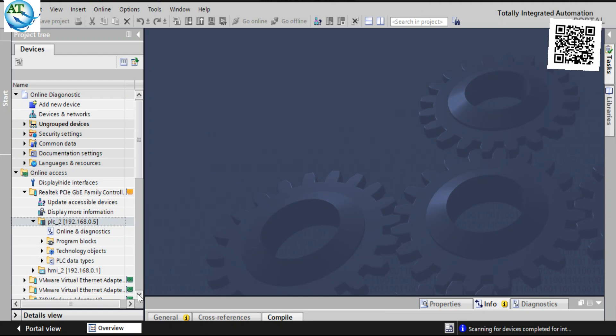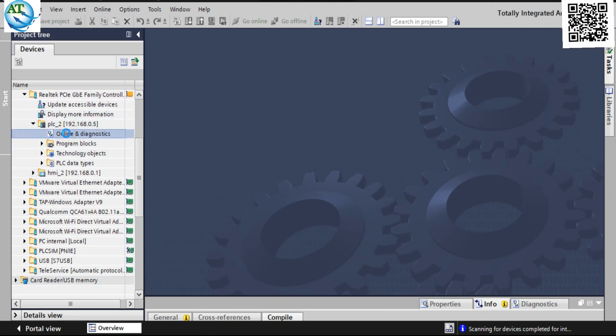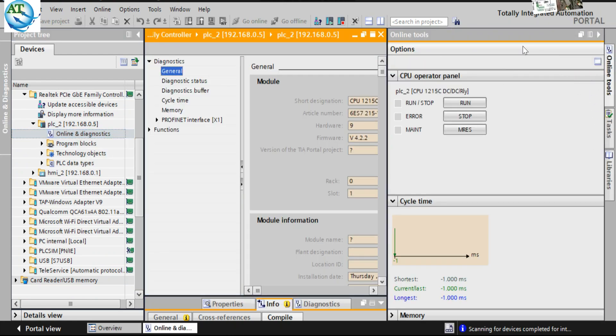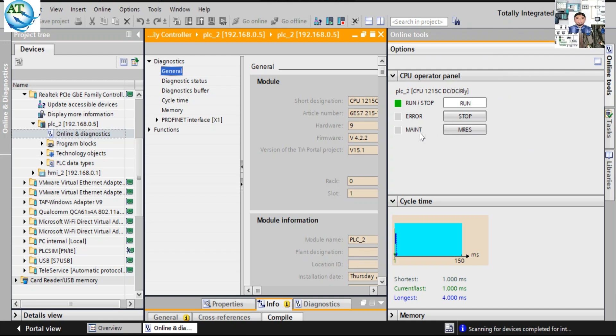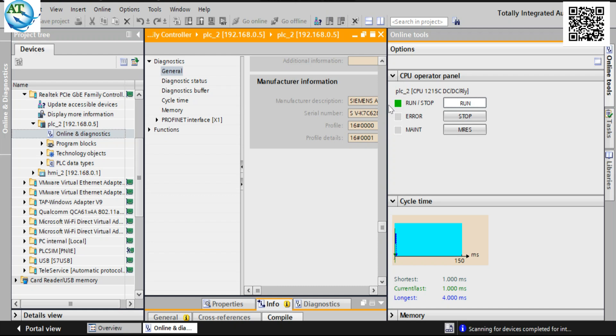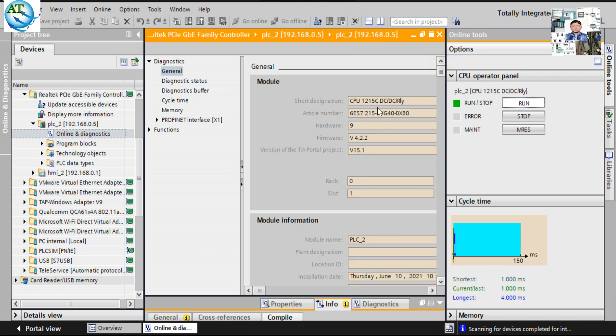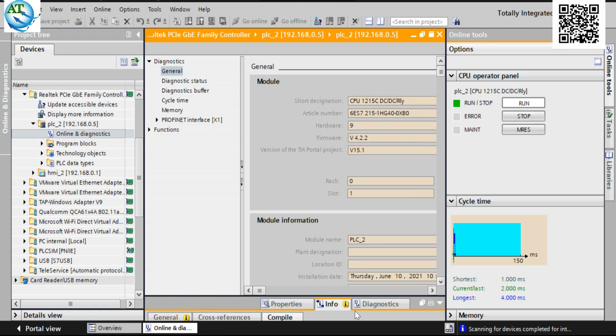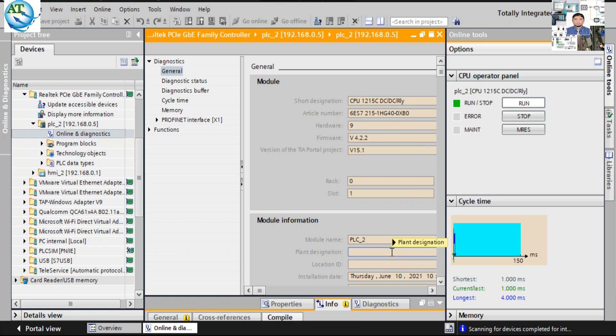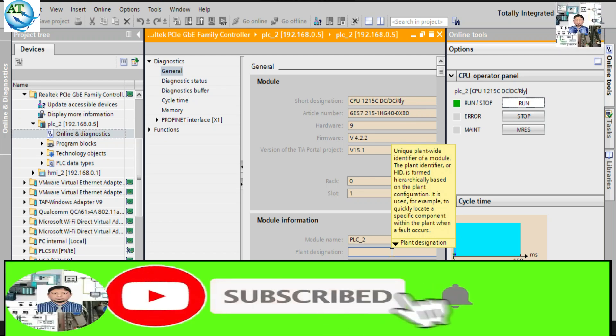I will show step-by-step how to determine if any fault is happening in this CPU. If you find any alarm in the LED system, press Online and Diagnostics. Then you can see the status of this CPU. The CPU is showing Run mode, and you can see the green LED on the right side. That means the PLC is in Run mode with no error and no maintenance error. If there is any error or maintenance error, the LED will change color. Here you can also see the identification information and the model number of this CPU, which is very helpful when you need to procure a new CPU — you can use this part number. You can see the part number, version number, and hardware number here. That means our CPU is running in that state.